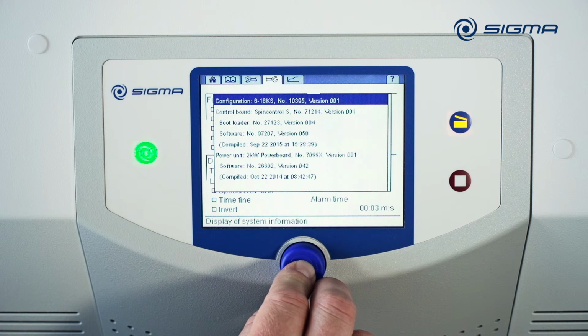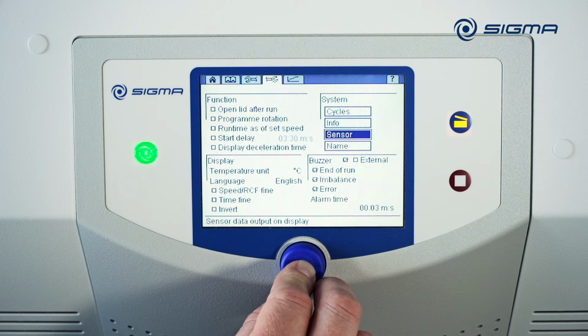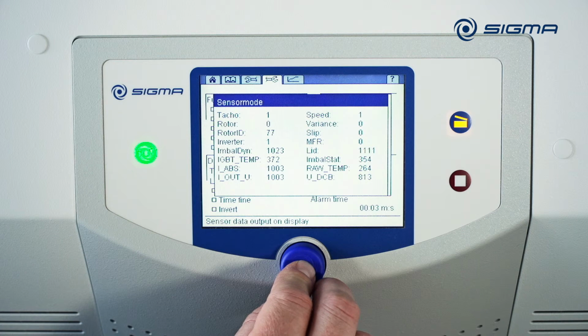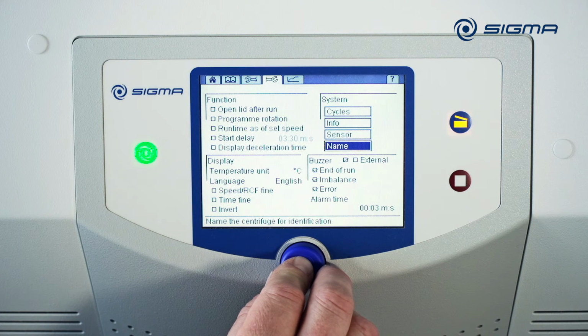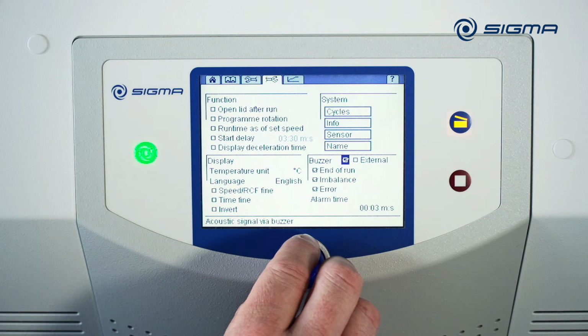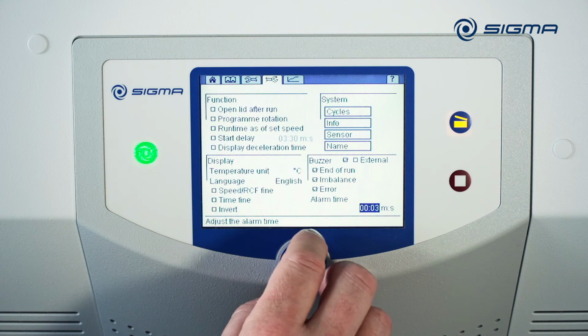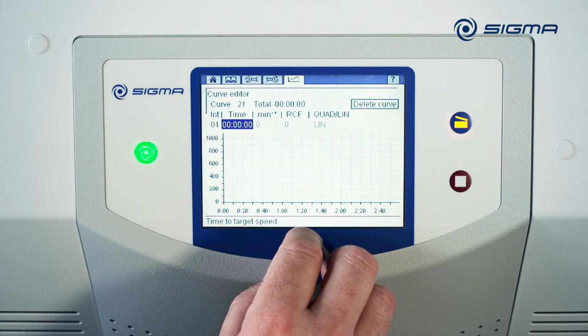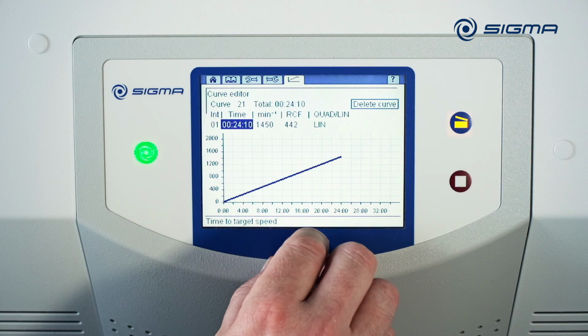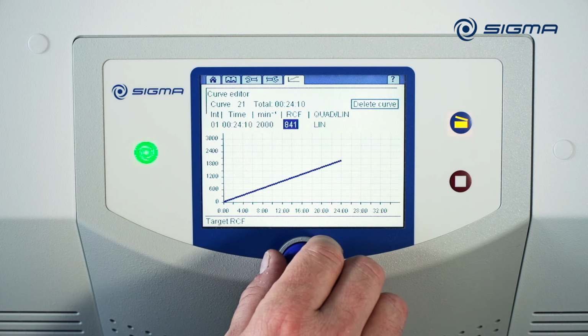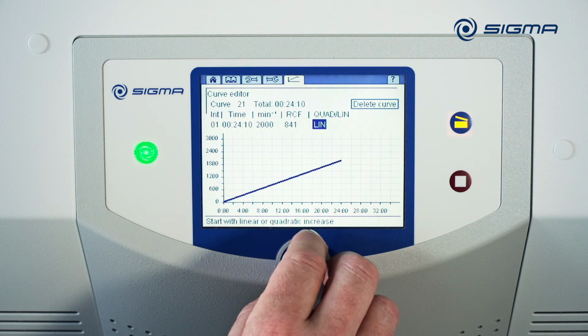The software version of the centrifuge is shown in the Info field. The Sensor Mode field shows the diagnostic codes which can be helpful for phone support in the event of problems. If the centrifuge is connected to a network, it can be assigned a name. If a run is terminated due to an imbalance or a fault, the centrifuge can emit an audible signal. The signal duration is configurable. In the curve editor shown here, you can freely define the braking period and rotor speed for deceleration to standstill. You can choose from a linear or quadratic curve for the final 1000 revolutions.